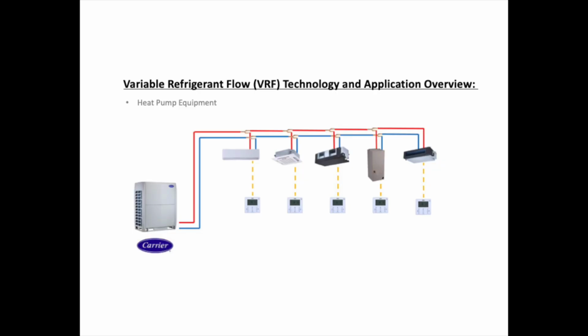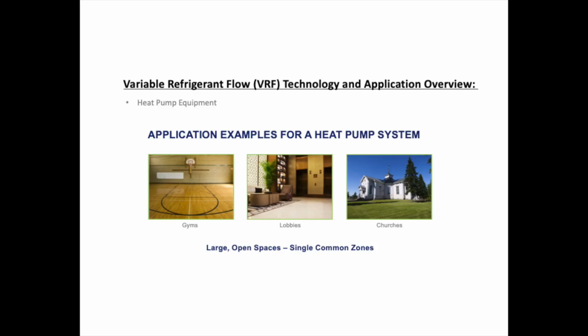Here's a general piping diagram for a heat pump system. You have your outdoor unit, you have your two pipes going from the outdoor unit to the inside space, and you have your Y branches that split off and go to each individual fan coil, and each fan coil is connected to its own remote controller. So what are good applications for a heat pump? Basically anything that has a large open space or a single common area. So churches, lobbies, bullpen areas in an office building with a large common area with cubicles. These are all good candidates for a heat pump system, since they will most likely be in either one mode or the other, either heating or cooling.